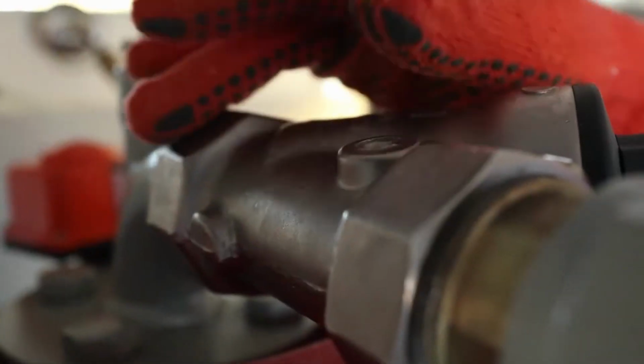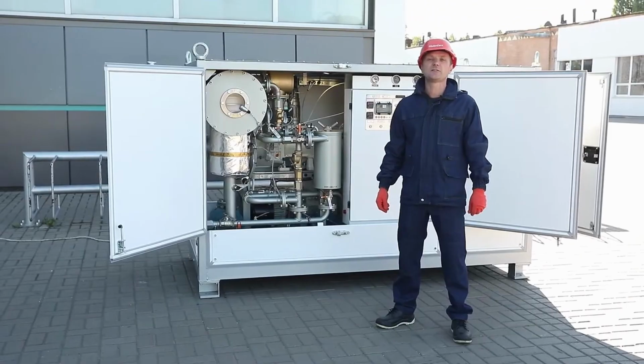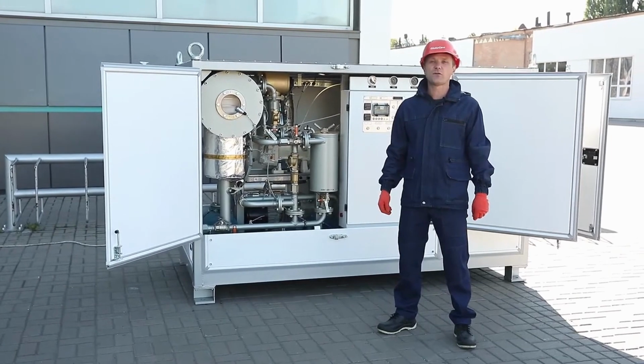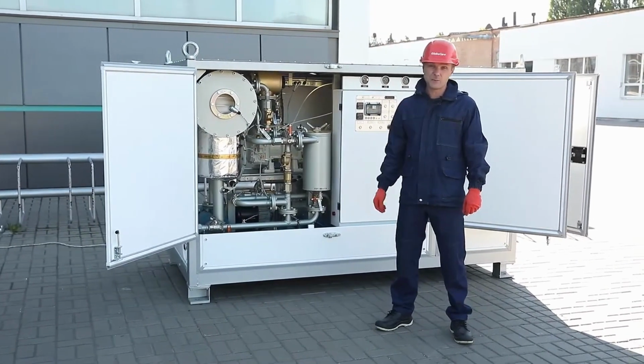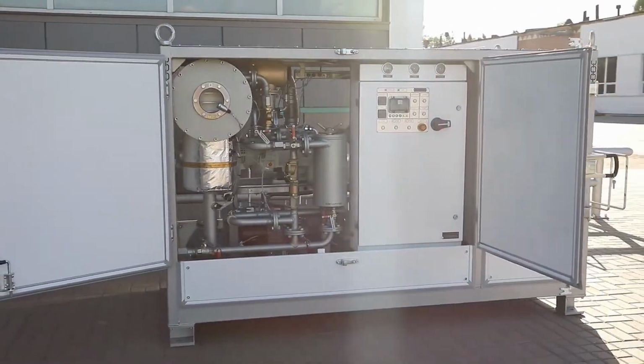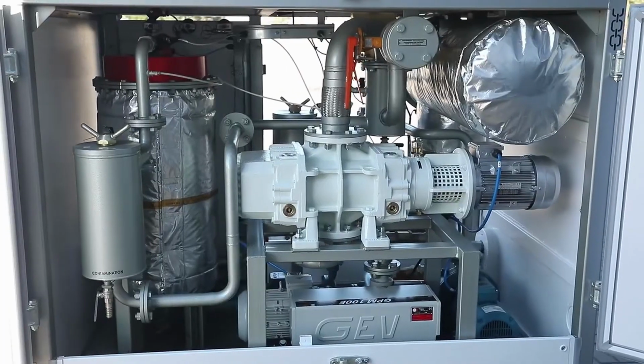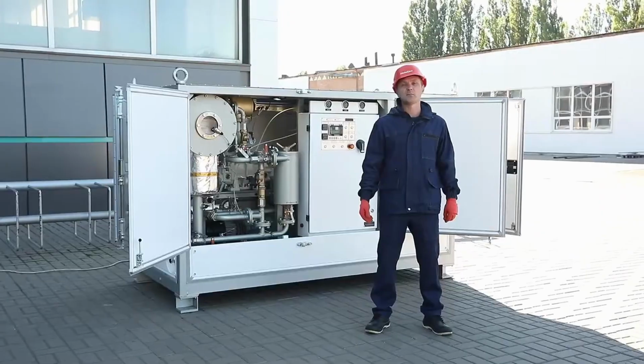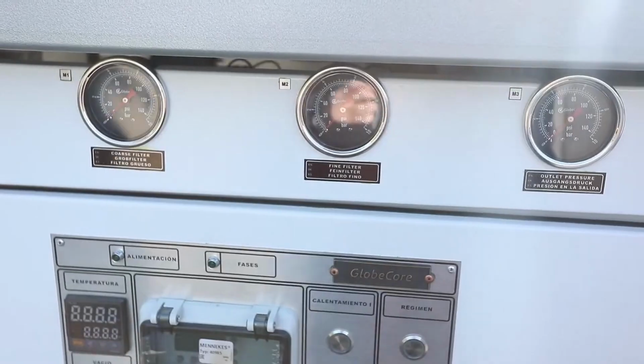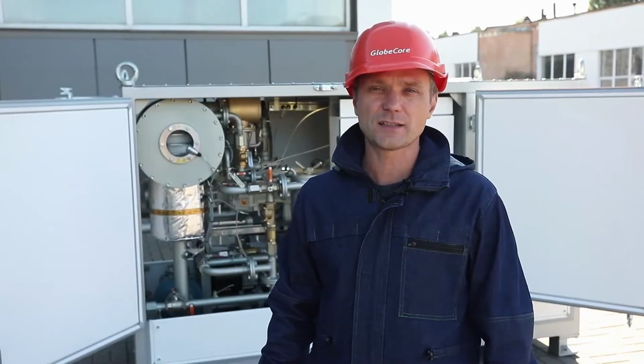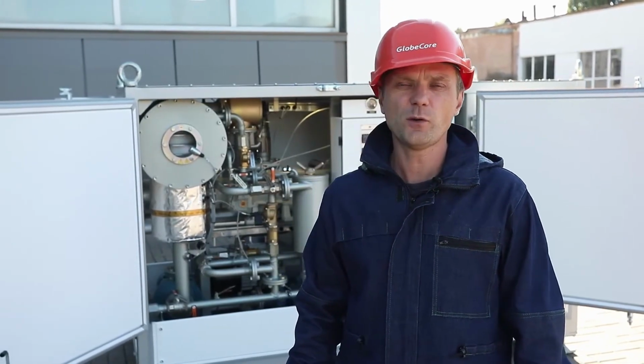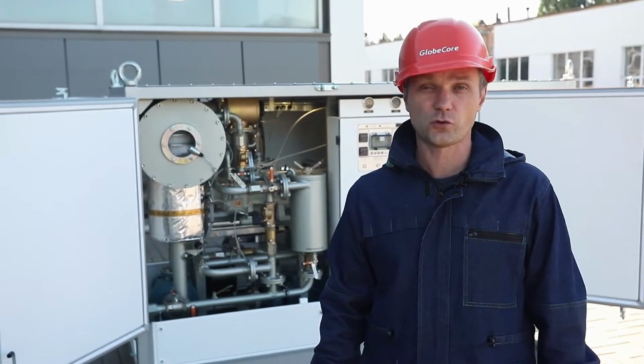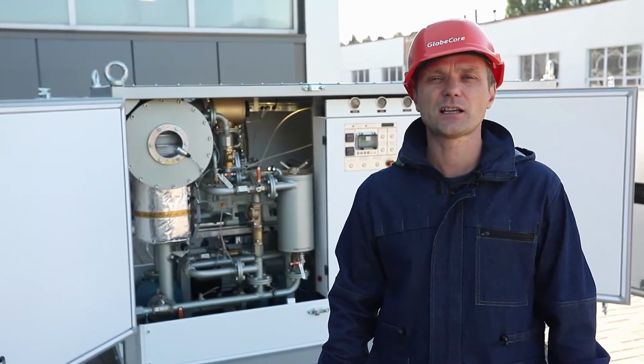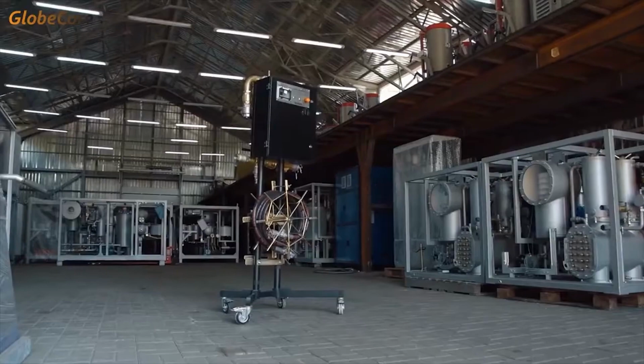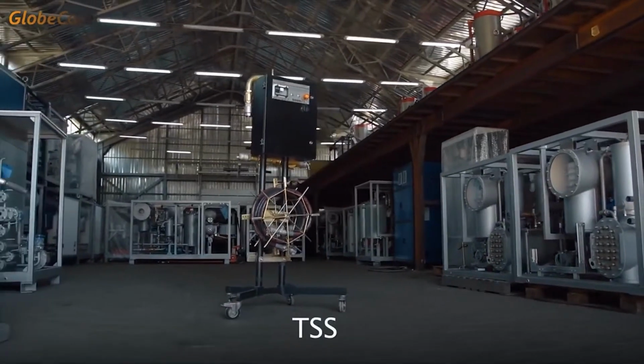With regard to design and automation degree, here you have a choice. We can place the unit into the container and mount it on the trailer. We can optionally make it automatic or semi-automatic with adjustment of capacity by means of valves. When using the automatically controlled unit, you get an additional bonus. By means of this unit, you can purify the oil in the operating transformer. In order to do this, it is enough to connect the unit to the transformer via the TSS safety system.